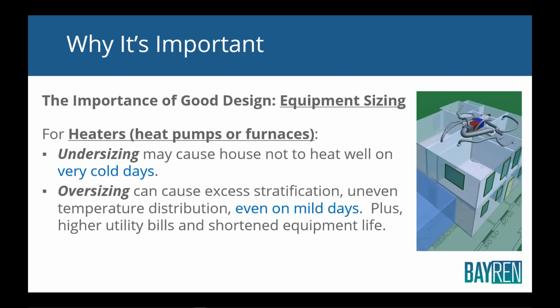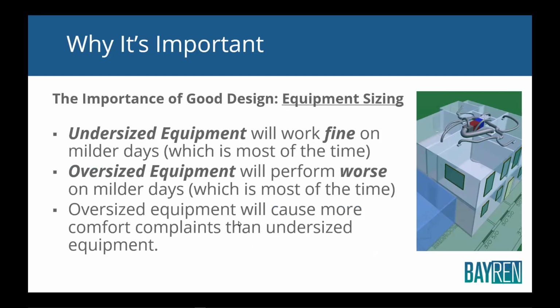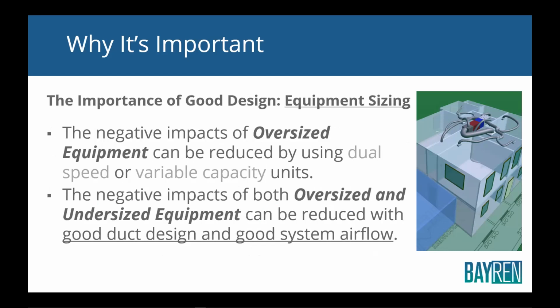For heaters, heat pumps, or furnaces, again, if you undersize, the house will work fine. It'll only not heat well on the very cold days, but oversizing, again, can cause issues on the mild days, which is most of the time. So oversizing will cause more comfort complaints. Undersized equipment will work fine on milder days, and oversized equipment will perform worse on milder days, which is most of the time, okay? So hopefully I've beat that dead horse and convinced you that oversized equipment is a problem.